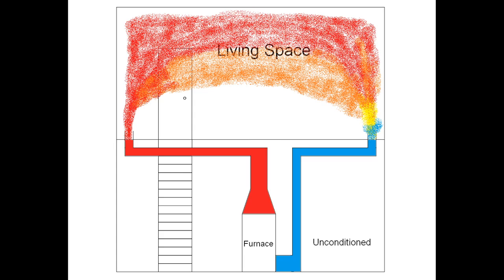Does that mean the living space is perfect? No. It can have cold spots because of windows, which honestly, if there are two, they're doing pretty well. Older windows have an R1, 1.5. Replacing a window may not get you anything substantial in terms of comfort, but it certainly will be costly. So the thermal gradient is one reason. From floor to ceiling can often be several degrees F.